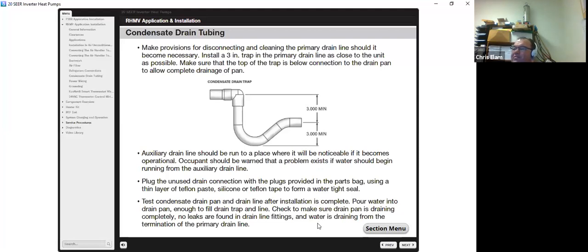It is important to test your condensate drain pan and drain line after installation is complete. Pour water into the drain pan, enough to fill the drain trap and line. Check to make sure the drain pan is draining completely and no leaks are found on your drain line fittings, and water is draining from the termination of the primary line.